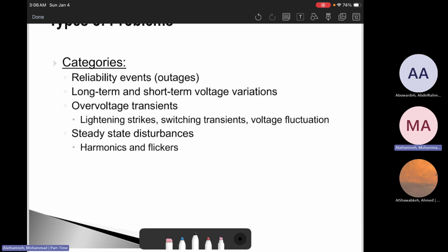The other thing: long-term and short-term voltage variations. Short-term can include sags and swells, which can happen from faults, motor startup, again, as we say, the high startup current of the motors, or capacitor switching turned on and turned off. The long term can include undervoltage or overvoltage due to loading, regulator settings, or feeder designs, especially at the end customer of long feeders. These are permanent, or I would say long-term, variations. In this situation, we need to fix it by changing the tap changer settings or doing voltage regulation, etc.